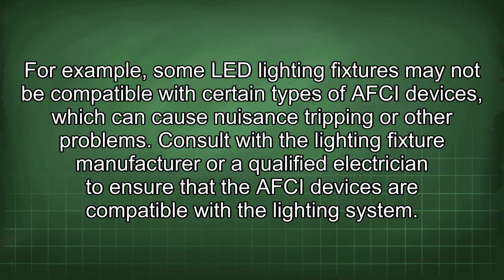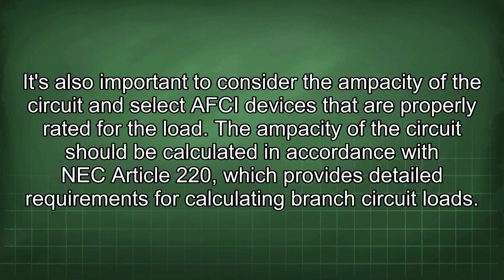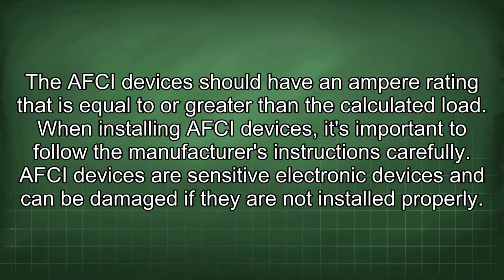Consult with a lighting fixture manufacturer or a qualified electrician to ensure that the AFCI devices are compatible with the lighting system. It's also important to consider the ampacity of the circuit and select AFCI devices that are properly rated for the load. The ampacity of the circuit should be calculated in accordance with NEC Article 220, which provides detailed requirements for calculating branch circuit loads. The AFCI devices should have an ampere rating that is equal to or greater than the calculated load.